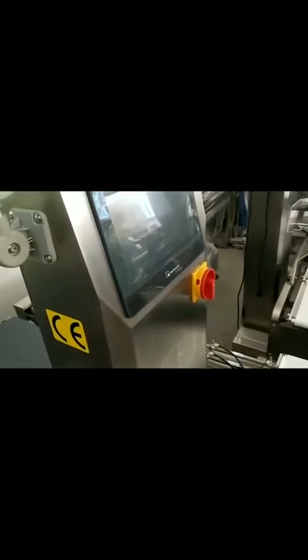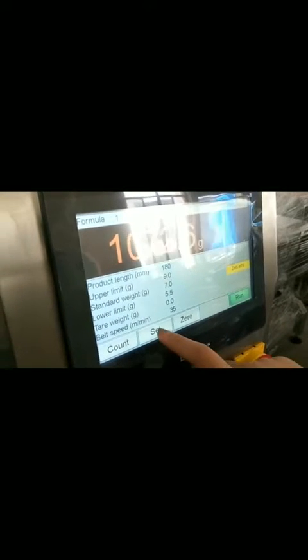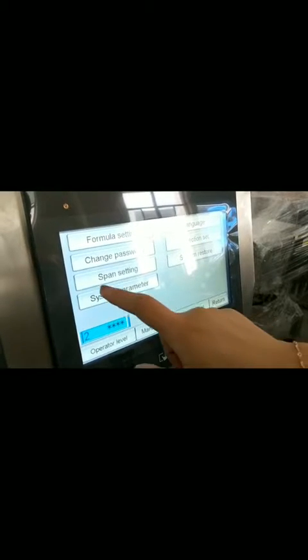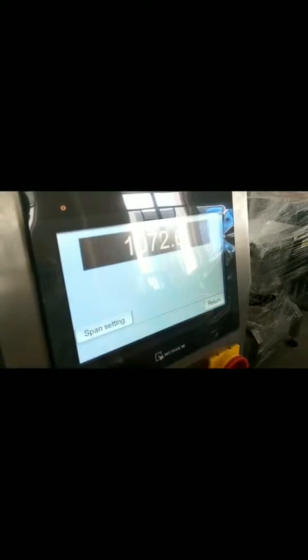After turning back on, we check if it can resolve the zero error. If not, we will need to do the calibration. Go to Settings, Service Level. Enter the 285H password. Enter. Go to Span setting.